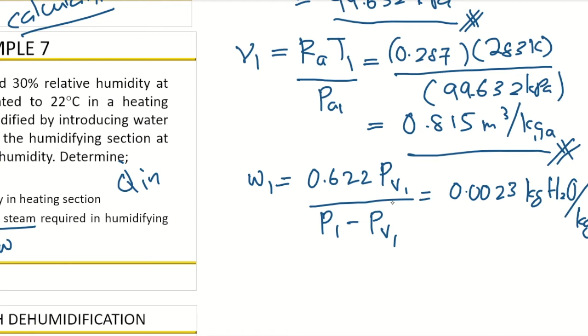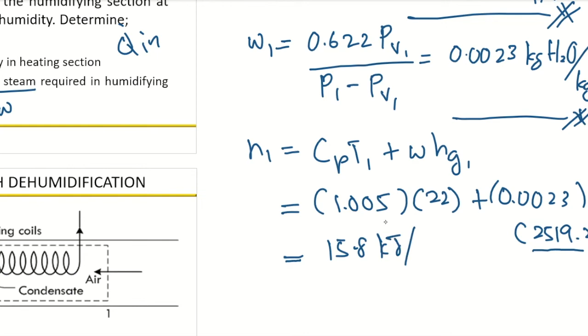Next is h1. It equals Cp T1 plus omega Hg1. So 1.005 is the specific heat, multiplied by 10, plus omega 0.0023 multiplied by Hg1, 2519.2. This value you need to determine from the property table, the enthalpy at saturation. So we go to the property table, 10 degrees C. This is saturation Hg, 2519.2. So h1 equals 15.8 kilojoule per kilogram dry air.